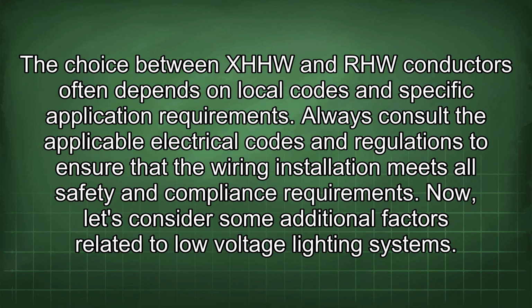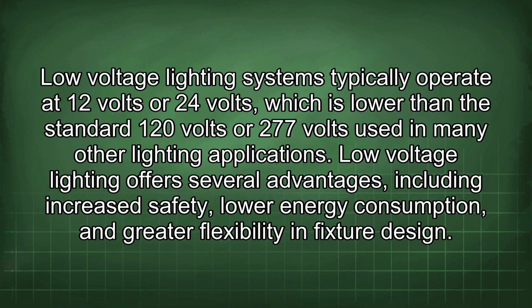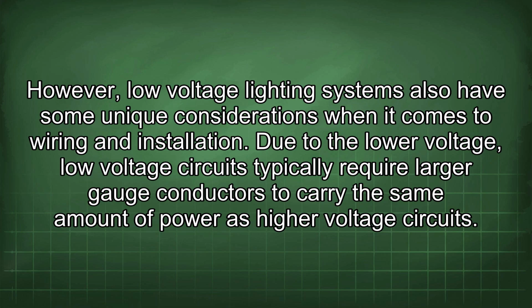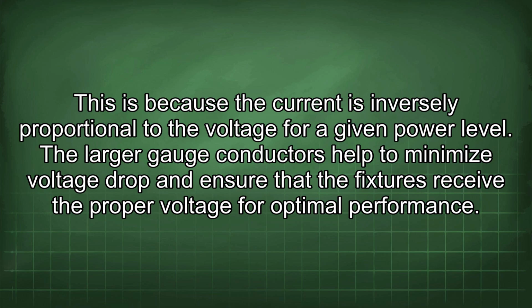Now let's consider some additional factors related to low-voltage lighting systems. Low-voltage lighting systems typically operate at 12 volts or 24 volts, which is lower than the standard 120 volts or 277 volts used in many other lighting applications. Low-voltage lighting offers several advantages, including increased safety, lower energy consumption, and greater flexibility in fixture design. However, low-voltage lighting systems also have some unique considerations when it comes to wiring and installation. Due to the lower voltage, low-voltage circuits typically require larger gauge conductors to carry the same amount of power as higher voltage circuits. This is because the current is inversely proportional to the voltage for a given power level.